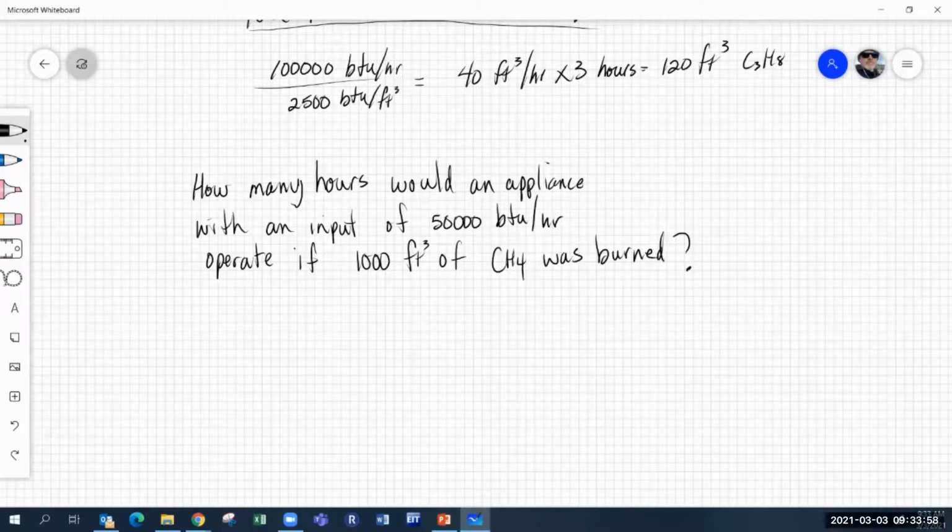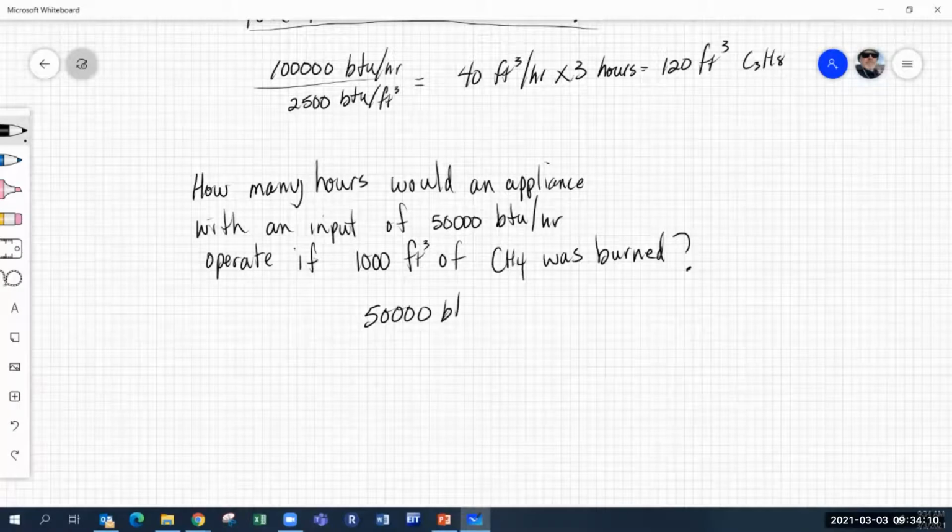I just saw it from the ILM on page 17. Come on, I want you to do the math. So you would take the 1,000 feet times 1,000 calorific value, gets a million, and then you take the million divided by the 50,000 BTUs per hour gives you the amount of hours.